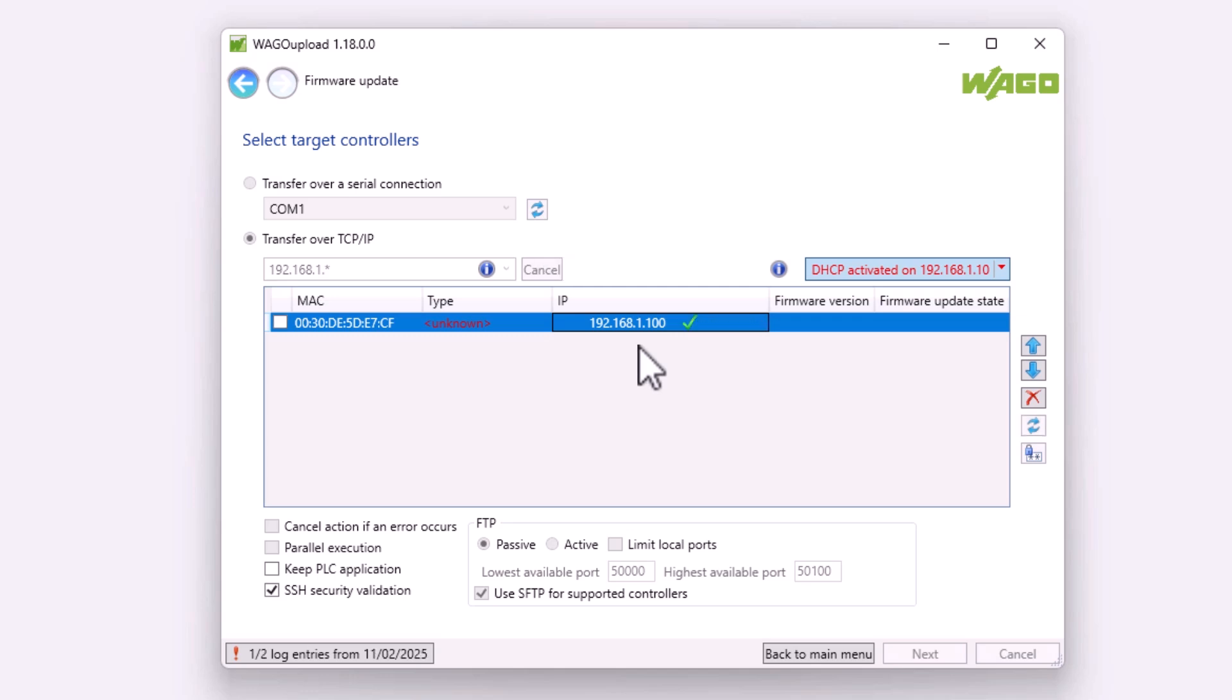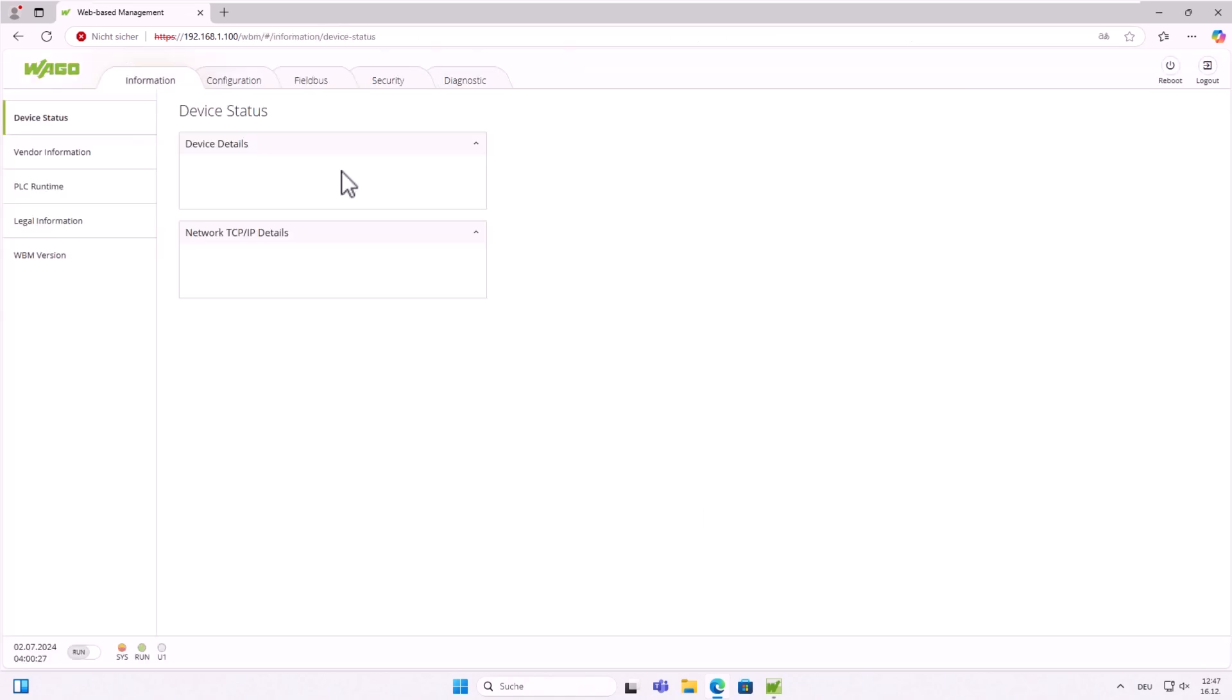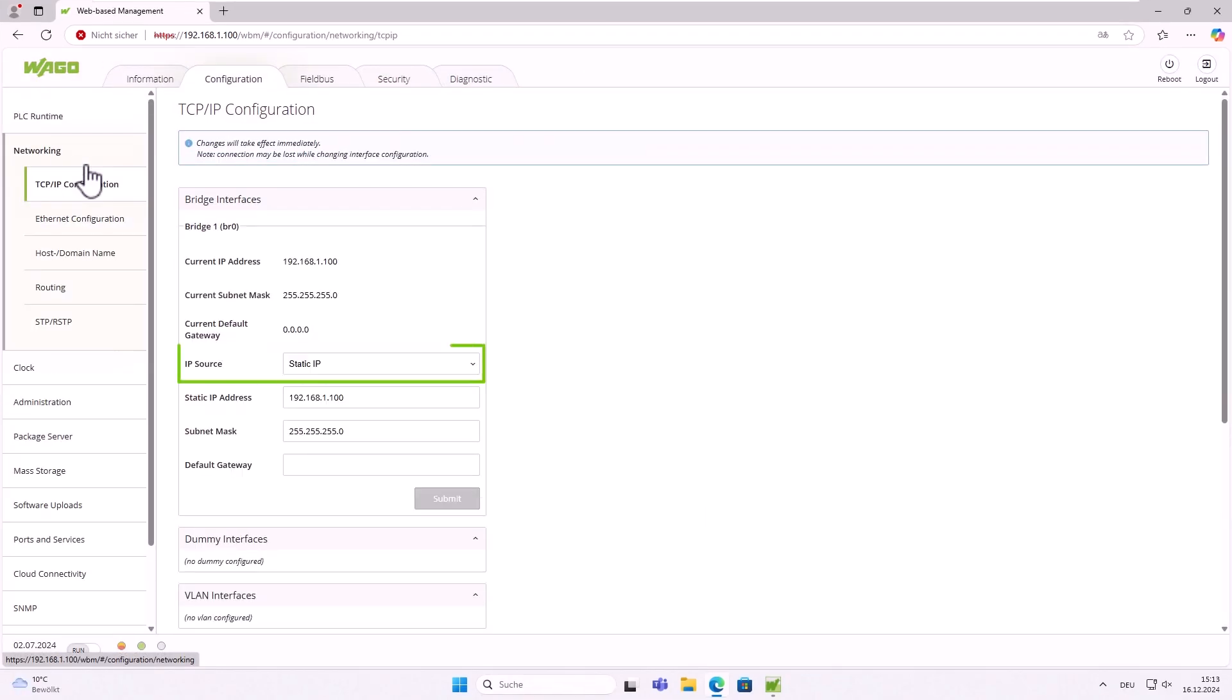The DHCP function can be disabled, and when we search for the controller using the IP address, it will be found. There is another important feature we would like to show you. If we now connect to Ethernet settings or WBM, we can see that the controller has been configured with a static IP address in the network settings. This is because WAGO Upload can find a controller configured with DHCP, but if you then assign an IP address to it, it will be assigned as a static IP address. If you want to get the controller back to DHCP, you have to reset it in the WBM or with Ethernet settings.